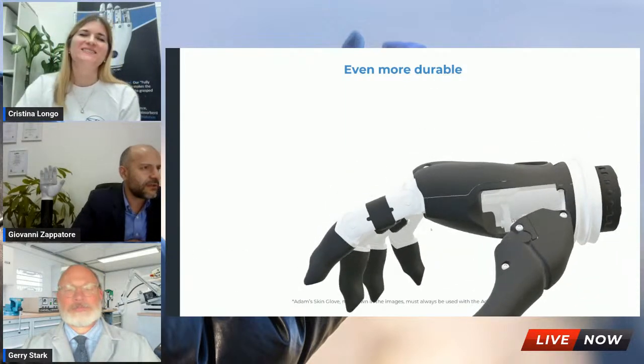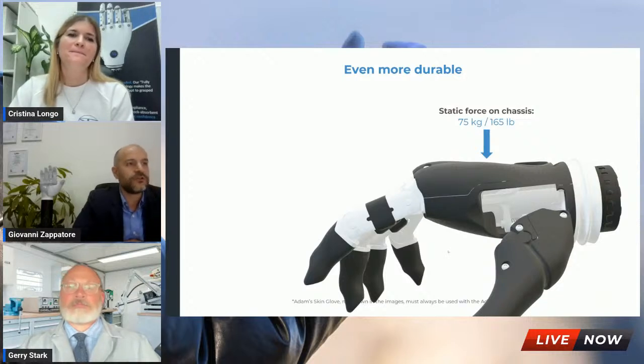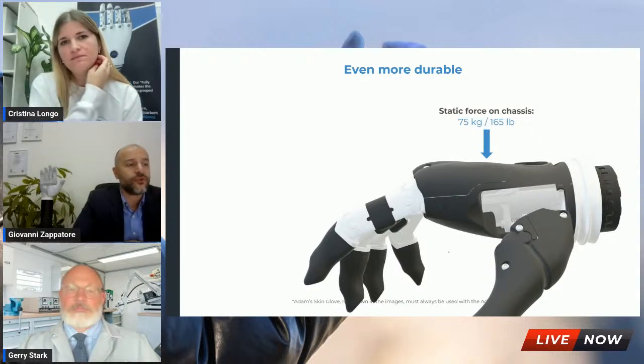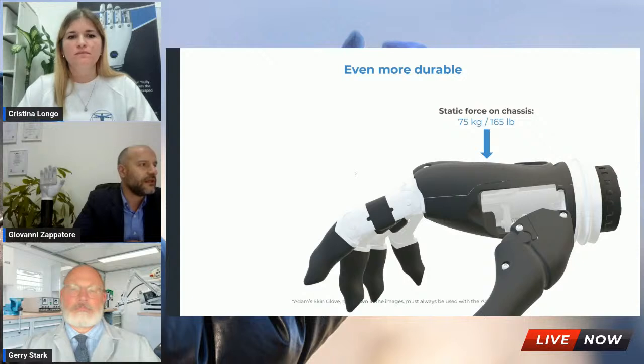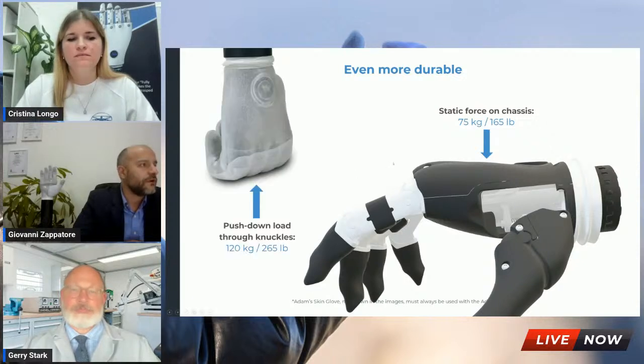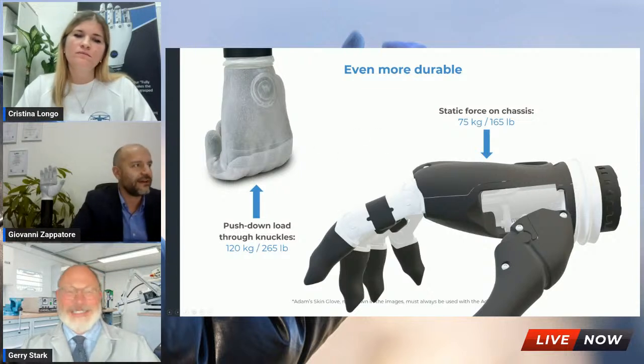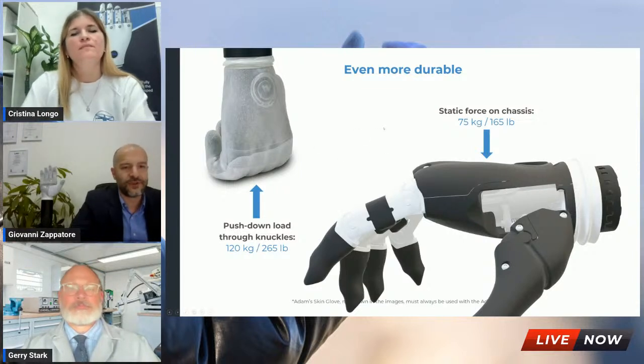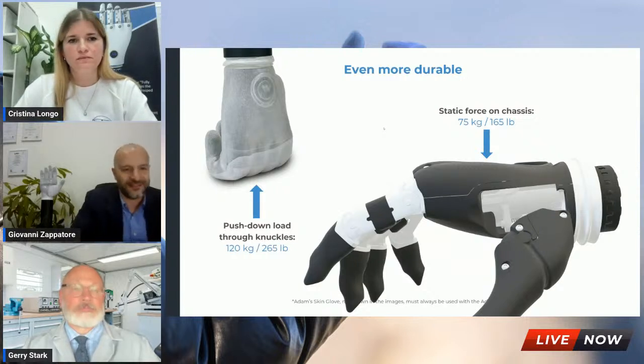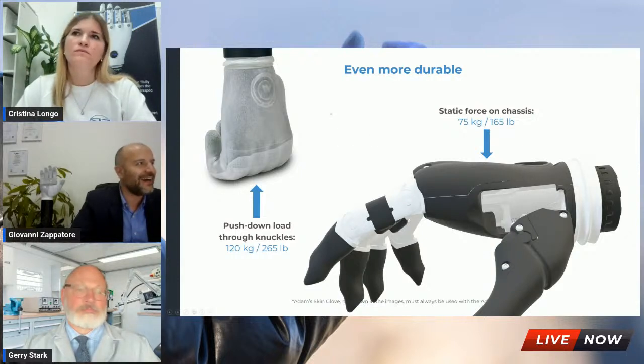Yes, then another couple of data points: 75 kilos or 160 pounds of static force on the chassis, and then the one that Jerry was citing before, the push down load for knuckles, which is 120 kilos or 260 pounds. So impressive. Yeah, quite high. It's quite safe, also when doing push-ups, as you've seen in the video before with Viviana, and for sure it gives us a lot of trust when speaking with users and with clinicians.